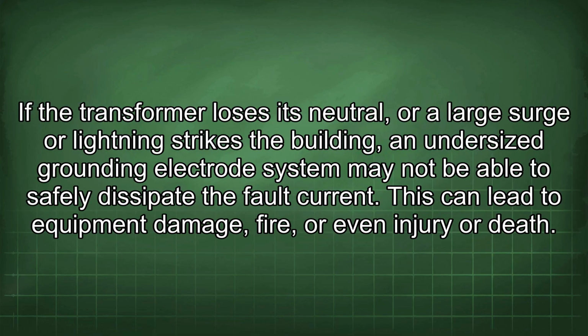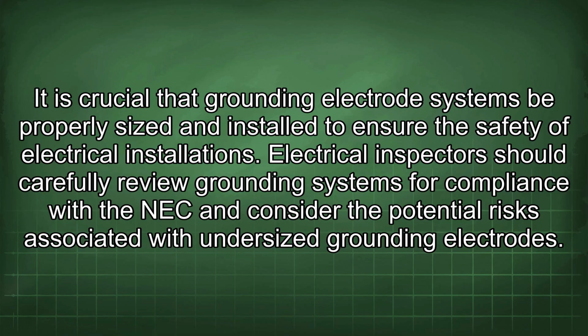250.66. If the transformer loses its neutral, or a large surge or lightning strikes the building, an undersized grounding electrode system may not be able to safely dissipate the fault current. This can lead to equipment damage, fire, or even injury or death. It is crucial that grounding electrode systems be properly sized and installed to ensure the safety of electrical installations.